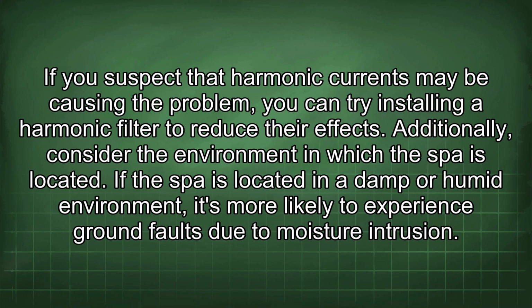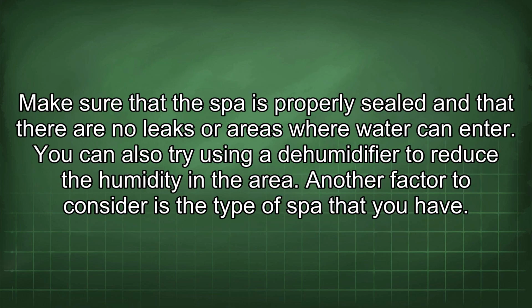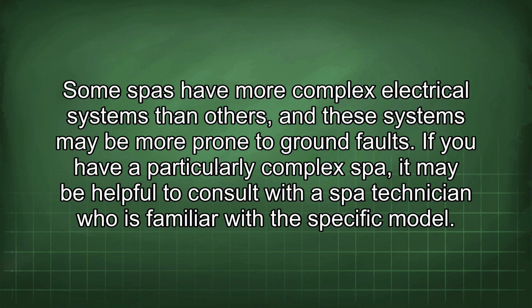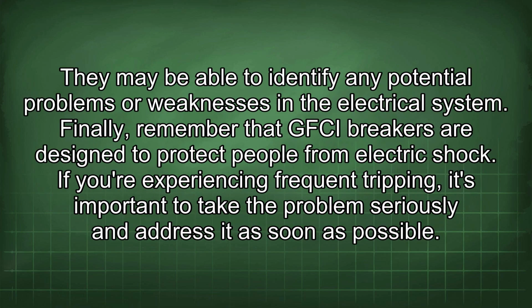If the spa is located in a damp or humid environment, it's more likely to experience ground faults due to moisture intrusion. Make sure that the spa is properly sealed and that there are no leaks or areas where water can enter. You can also try using a dehumidifier to reduce the humidity in the area. Another factor to consider is the type of spa that you have. Some spas have more complex electrical systems than others, and these systems may be more prone to ground faults. If you have a particularly complex spa, it may be helpful to consult with a spa technician who is familiar with the specific model. They may be able to identify any potential problems or weaknesses in the electrical system.